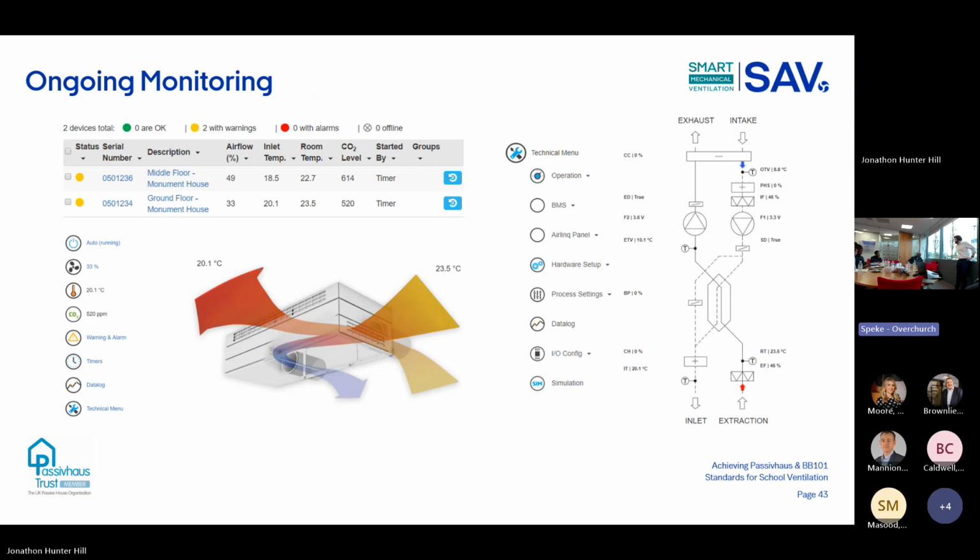Another question. In terms of the inlet and exhaust air, how does this unit reduce cross-contamination? So the calculated cross-contamination between intake and exhaust is a maximum of 4%. In practice, it's been measured at less than that, but the way it does it is we have the two external connections. They're about 1.8 meters apart. On the intake, the fan is located quite far into the unit, so the pressure at the spigot is actually quite low. Whereas on the exhaust, the fan is located right at the spigot. So at the exhaust, it shoots out the air as a jet at very high velocity and a high pressure. So because of the vast differences in pressure and also this jet, we find they don't really recirculate at all.